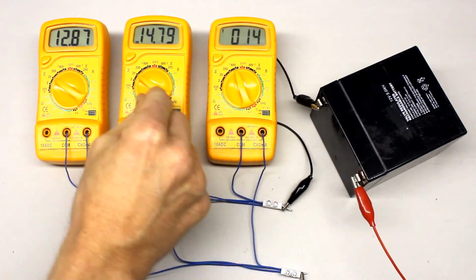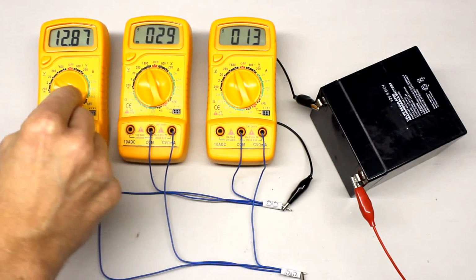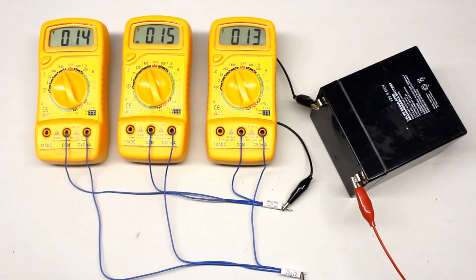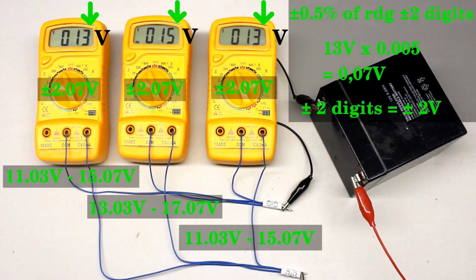If the multimeter is set to the 600 volts range, the least significant digit corresponds to 1 volt, while the percentage of reading doesn't change significantly. 1 digit represents 1 volt, hence a total error of more than 2 volts has to be considered. Selecting the lowest measurement range possible reduces the negative effect of least significant digits and gives the most accurate results.